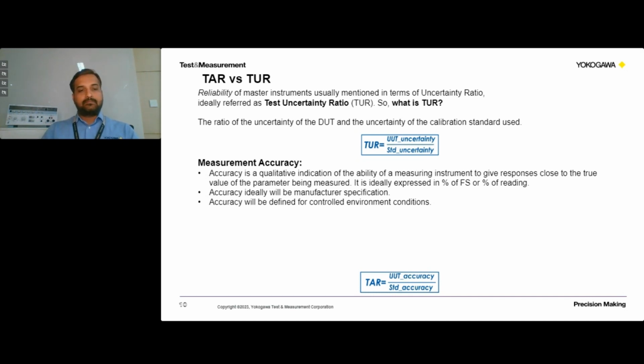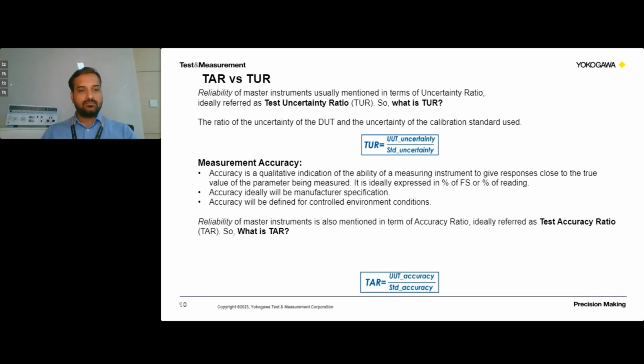And accuracy is basically the manufacturer's specification. When we compare uncertainty to accuracy, in uncertainty we are further considering the errors which arise because of all the other factors which we discussed in the previous slide. The reliability of the master instrument is also defined by test accuracy ratio. Test accuracy ratio is the accuracy of the DUT compared to the accuracy of the standard which we are using.